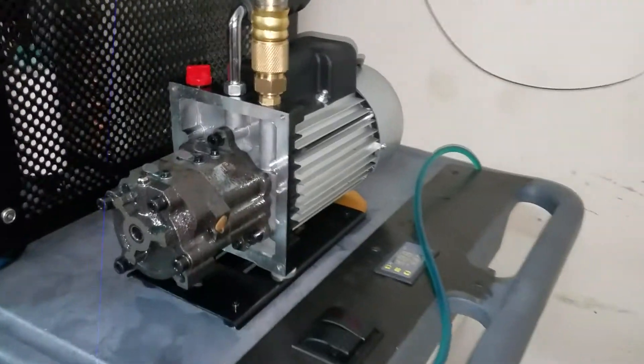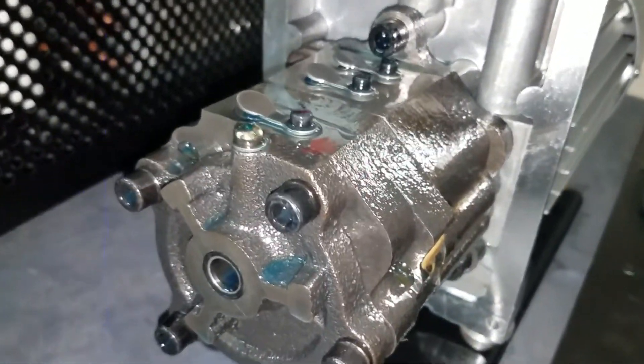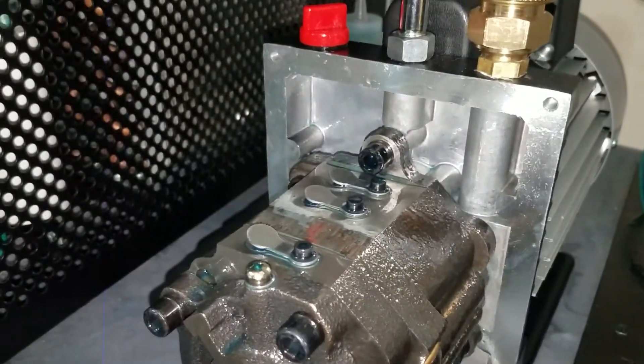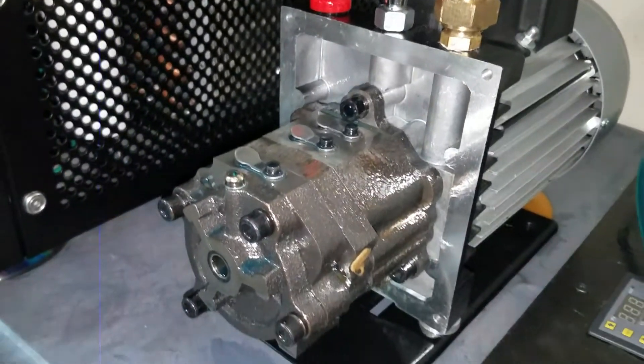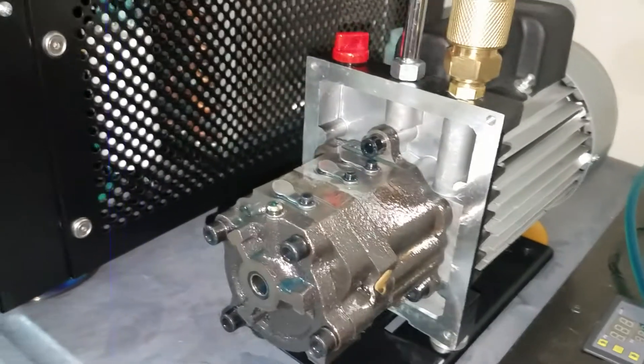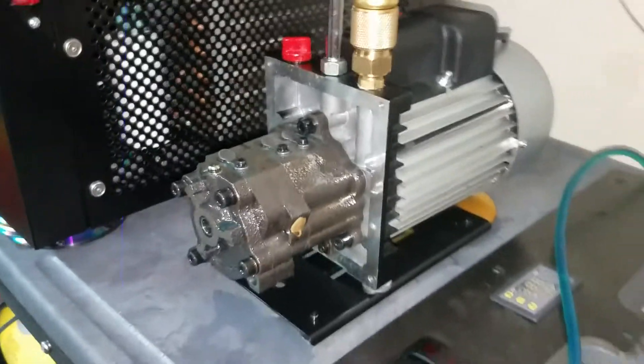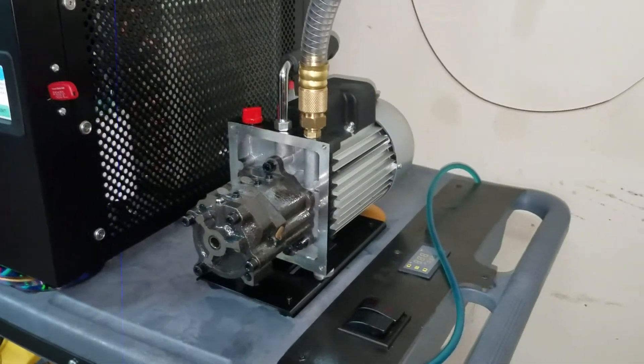It's very important to pull the water out of the oil as soon as it coalesces in the bottom of the tank. By doing that, 60 batches in, it looks as pretty as the day it was brand new. We get 500 militorr in just under 5 minutes — about 4 minutes 40 seconds — which is the same as when it was brand new. We don't open it, we don't mess with it, we don't touch it. The pump likes it that way. More to follow. Thanks guys.